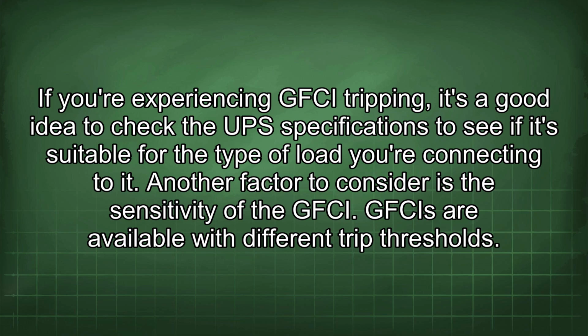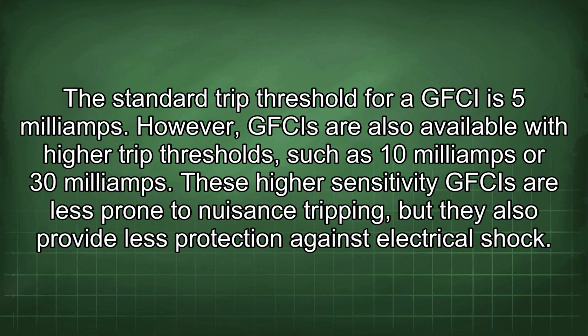Another factor to consider is the sensitivity of the GFCI. GFCIs are available with different trip thresholds. The standard trip threshold for a GFCI is 5 mA. However, GFCIs are also available with higher trip thresholds, such as 10 mA or 30 mA. These higher threshold GFCIs are less prone to nuisance tripping, but they also provide less protection against electrical shock.